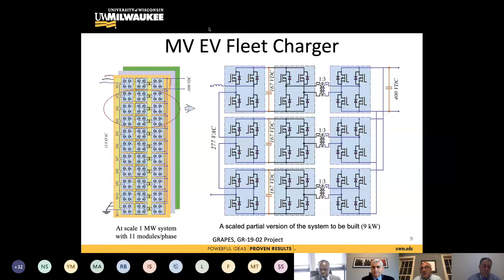The third project is moving the voltage and power of the dual active bridge to the limits that we are able to do. By that, we get the input voltage to 13 kilovolt DC and output voltage to 7.2 kilovolt DC. So the input, if you do that, you can connect to a single phase 13.8 kV utility voltage. At the output, you can get to the highest level of electrical distribution voltage in the US, which is 4160 three phase. So at the output you can use that.